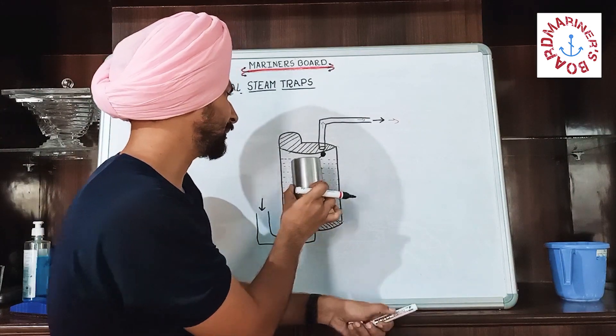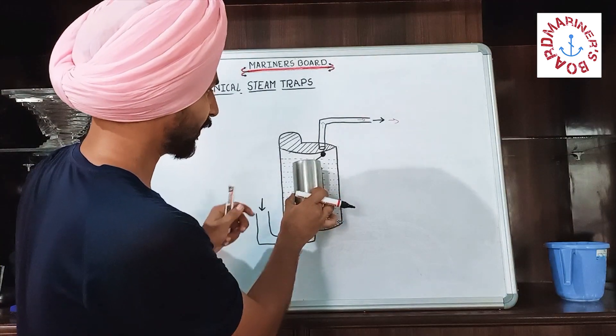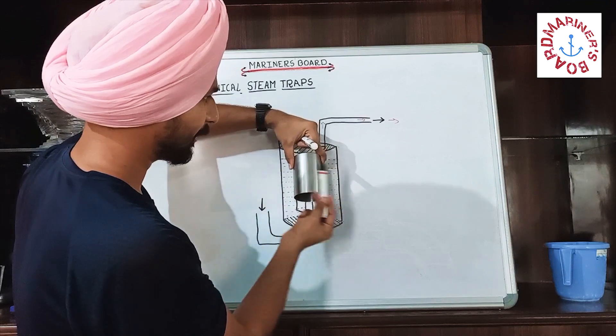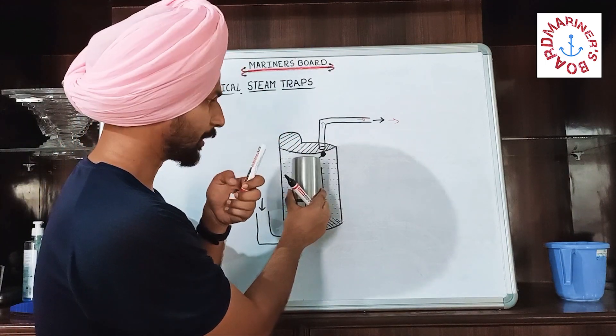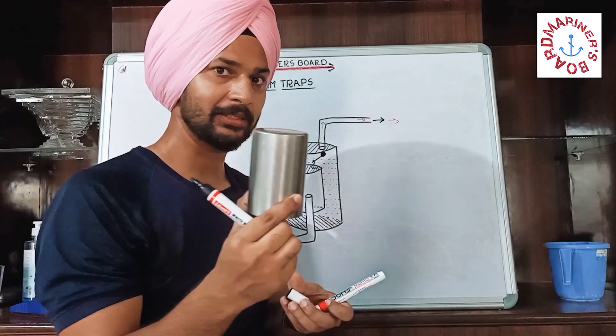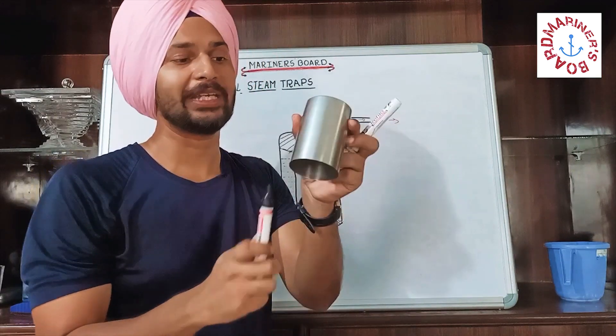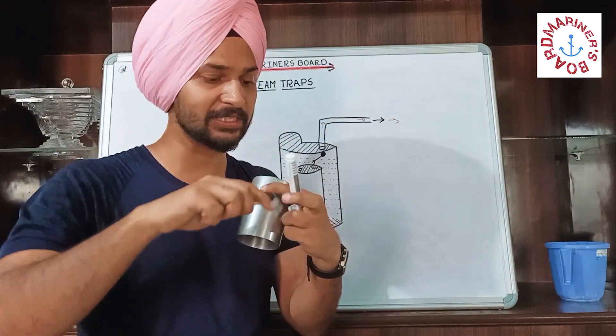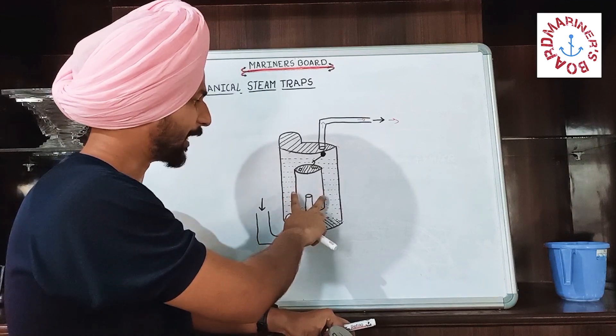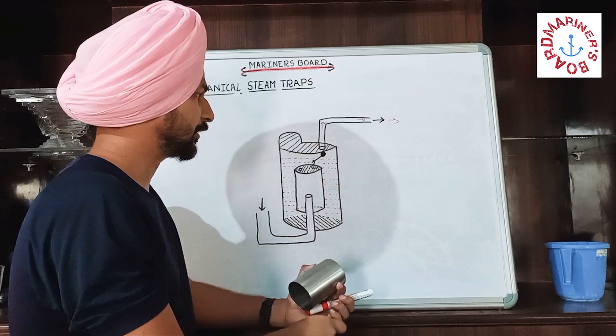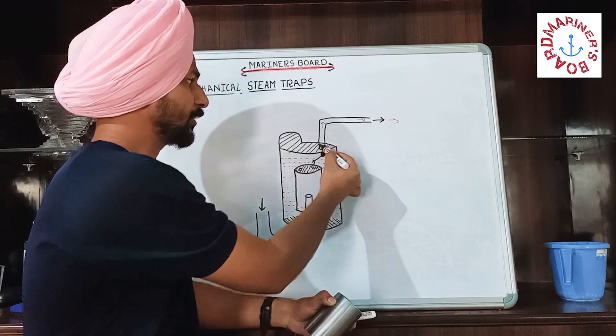In this type of steam trap, priming is required first. The space around the inverted bucket is always filled with water. Since air is inside the inverted bucket and it is empty, the buoyancy of the bucket is greater. Because of this greater buoyancy, the valve or ball moves upward and shuts the outlet, so nothing can go out.